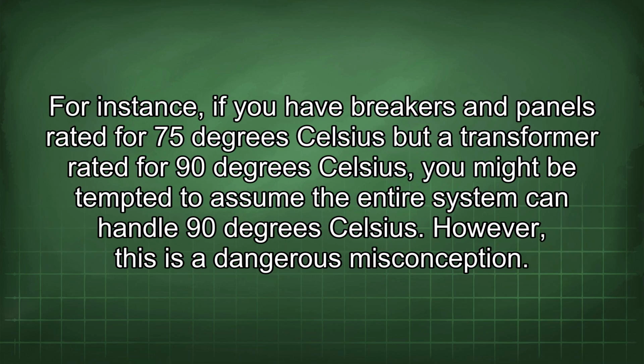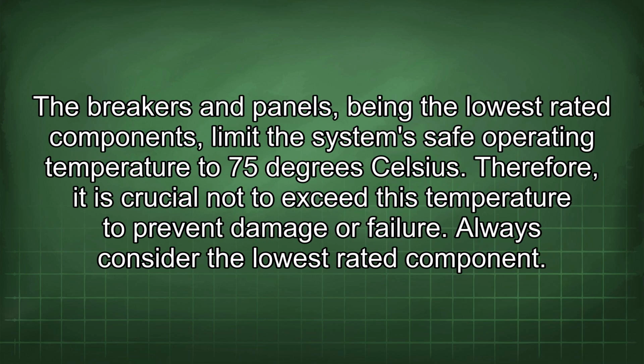For instance, if you have breakers and panels rated for 75 degrees Celsius but a transformer rated for 90 degrees Celsius, you might be tempted to assume the entire system can handle 90 degrees Celsius. However, this is a dangerous misconception. The breakers and panels, being the lowest rated components, limit the system's safe operating temperature to 75 degrees Celsius. Therefore, it is crucial not to exceed this temperature to prevent damage or failure. Always consider the lowest rated component.